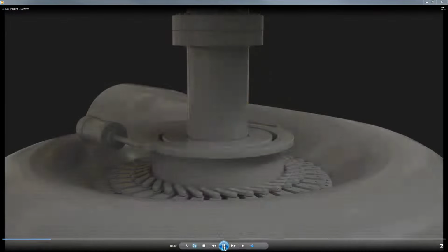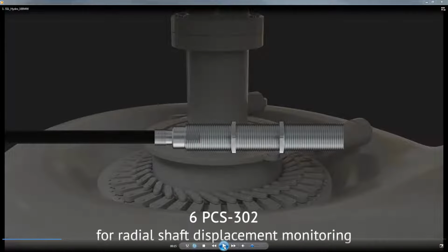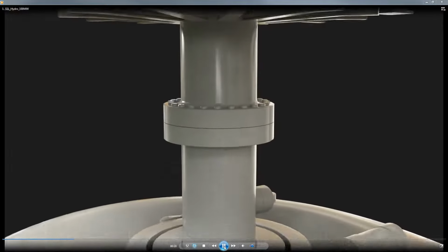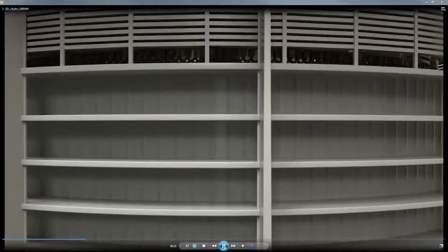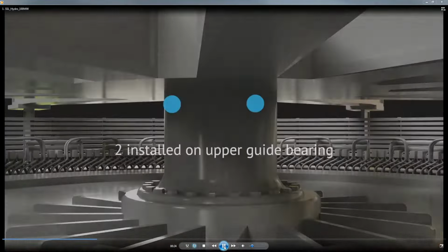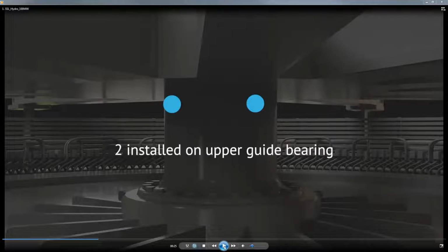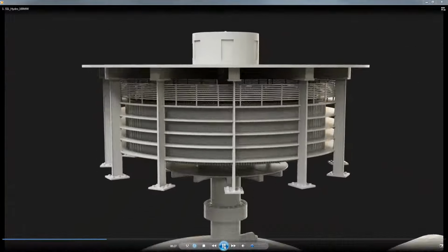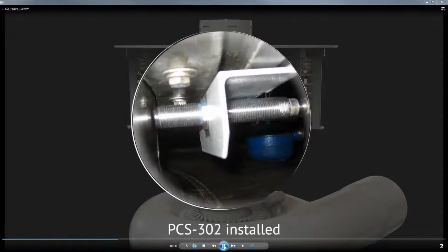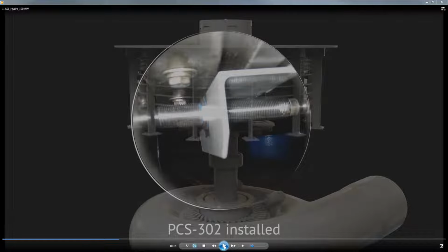Okay, I have an example here. Then what we recommend is shaft displacement probes, either 4 or 6. It says 6 here, which is the maximum number of sensors for hydro generators. 2 are installed in the XY format position in the turbine guide bearing, 2 are installed at the lower guide just below the rotor, and then 2 are installed at the upper guide bearing for units that are not umbrella type units and do have an upper guide bearing. So we have a total of 6. We have an example picture here. These are capacitive probes. We'll get into that in the slide part of the presentation.